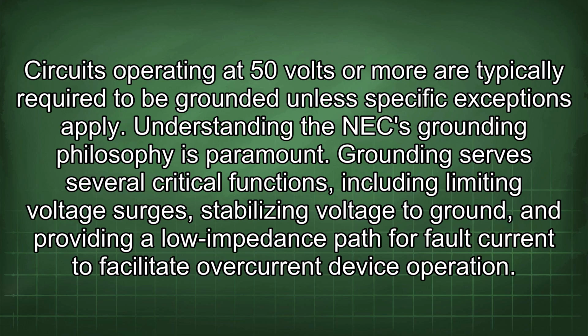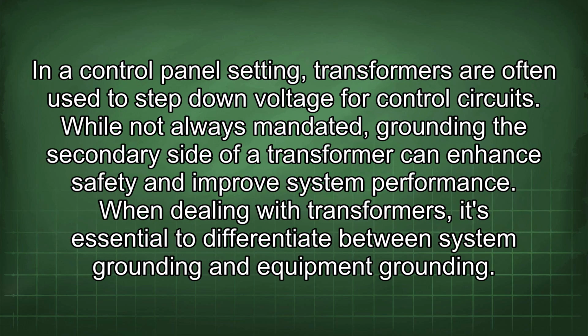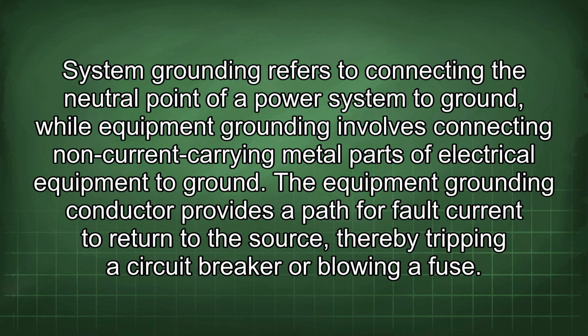Understanding the NEC grounding philosophy is paramount. Grounding serves several critical functions, including limiting voltage surges, stabilizing voltage to ground, and providing a low impedance path for fault current to facilitate overcurrent device operation. In a control panel setting, transformers are often used to step down voltage for control circuits. While not always mandated, grounding the secondary side of a transformer can enhance safety and improve system performance. When dealing with transformers, it's essential to differentiate between system grounding and equipment grounding. System grounding refers to connecting the neutral point of a power system to ground, while equipment grounding involves connecting non-current carrying metal parts of electrical equipment to ground.